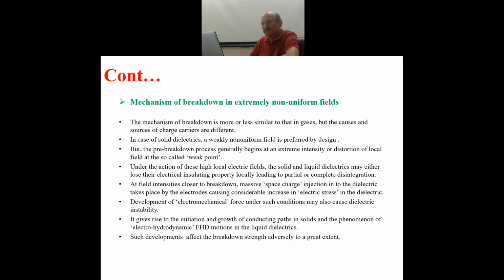You know that in extremely non-uniform field conditions, the breakdown always takes place with preceding partial breakdown phenomena. Breakdown directly would not take place in an extremely non-uniform field configuration. The breakdown would always take place with preceding partial breakdown phenomena. So that is true in all dielectrics. We discussed so much: the corona is nothing but partial breakdown in extremely non-uniform field.